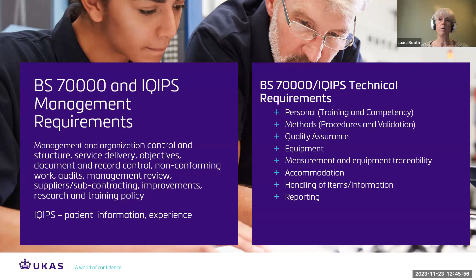And then the same really with the technical requirements. So when we're looking technically, we're looking at personnel, their training, their competence to deliver what they do, looking at methods and procedures, what QA they have in place, what equipment's in place, is there calibration, is that effectively measured, is there equipment traceability, uncertainty of measurement criteria, looking at the accommodation that you're providing the activity in, how you're handling particular systems, and reporting outcomes with regards to the activity that you deliver. So again, very transferable. And the benefit of BS 70,000 and IQIPS is that because the standards are aligned, there is the opportunity for us to perform assessments for an organisation for both standards at the same time, so that again, that can be a cost-saving, time-saving mechanism for you moving forward in the accreditation process.